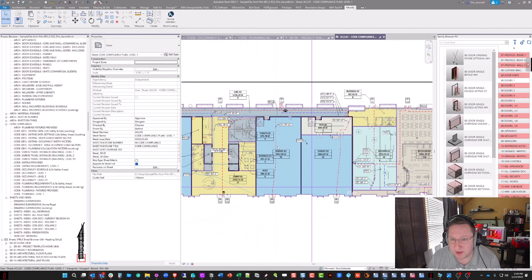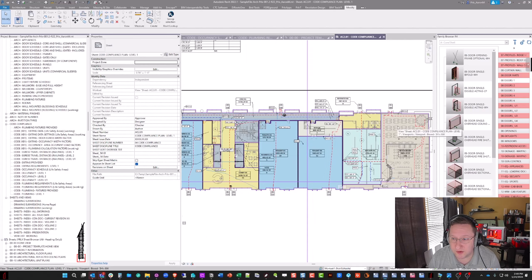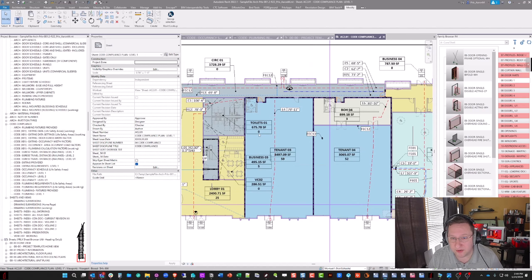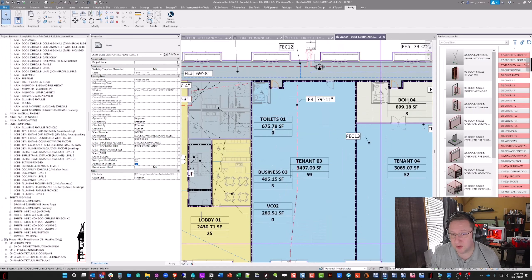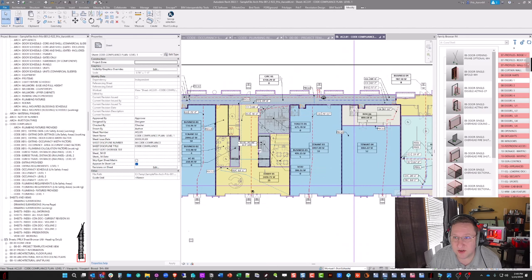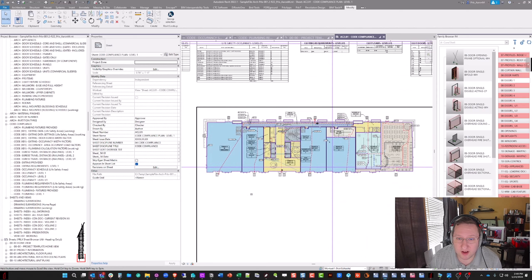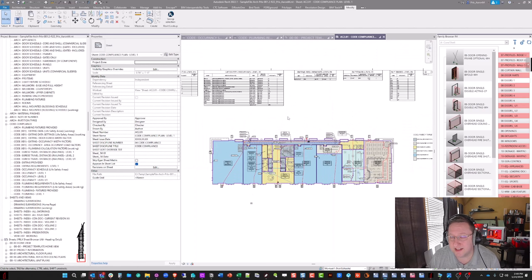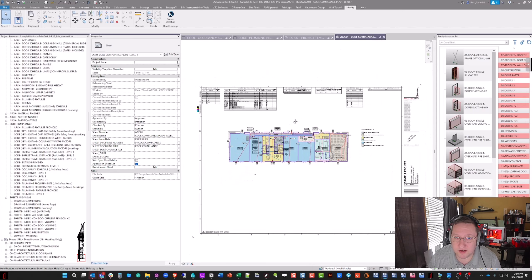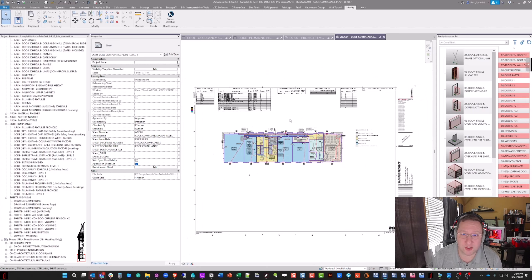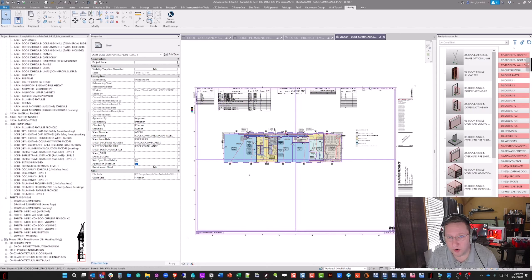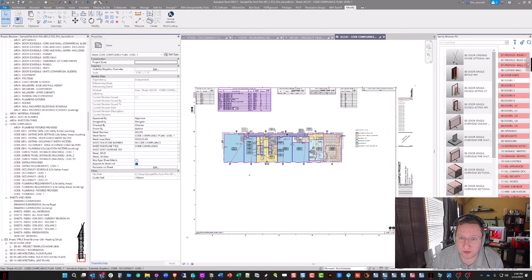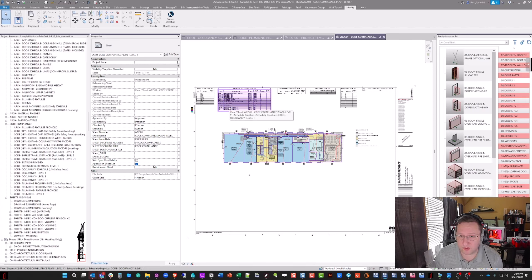All of these schedules fill themselves in based on a series of instructions covered in the training videos. It has to do with stepping through a series of schedules that ask you questions — such as assigning the occupant load factors to each area — and when you assign those, it generates the area per occupant and the occupants calculated on the fly. These are not things that get automatically typed in; they fill in based on selections you make. From there, you'll go into another schedule called plumbing requirements and similarly fill in a plumbing occupancy key, which will then calculate the number of plumbing fixtures that need to be present in the building on another code sheet.